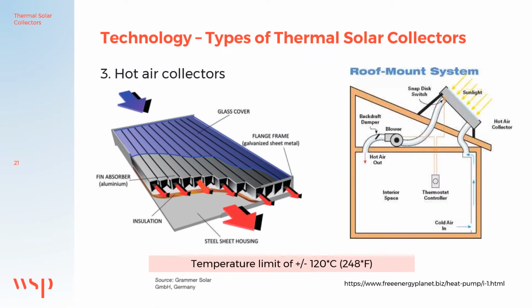I just want to mention a third technology which is called hot air collectors, where air flows through individual channels and is warmed up by the sun. These collectors typically have a glass cover with a backsheet housing and a thermal insulation just like flat plate collectors. This collector can reach air temperatures up to 120 degrees C or 248 degrees Fahrenheit. This technology is not commonly used worldwide, most probably because of the low heat capacity and density of air versus water. Water is 784 times denser than air.